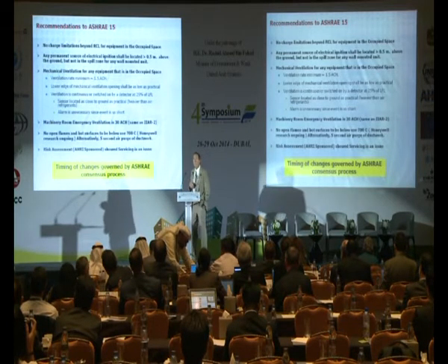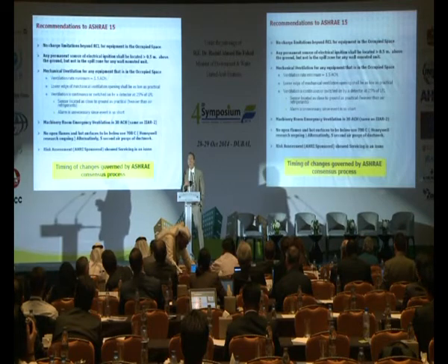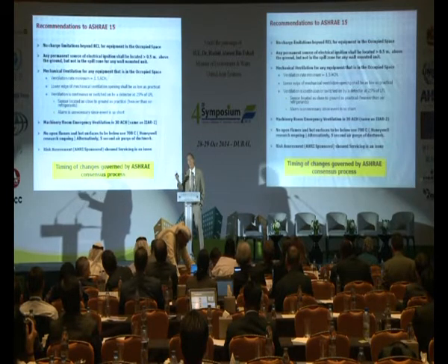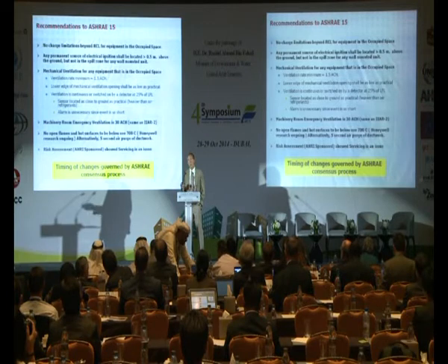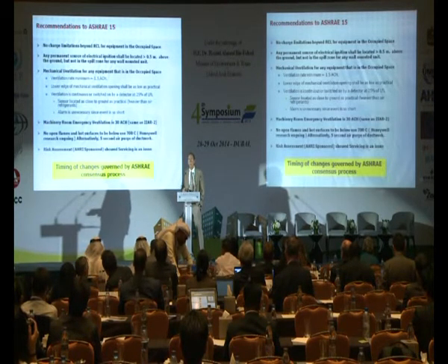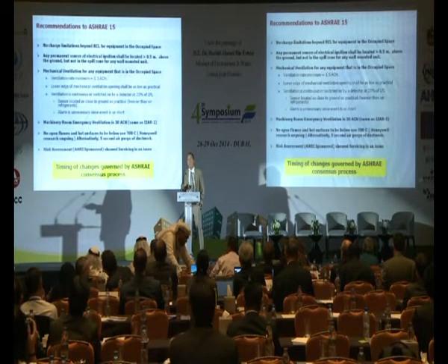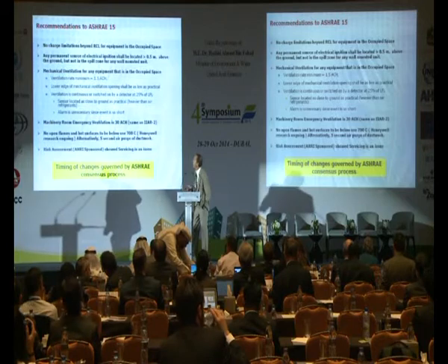For ASHRAE 15, we won't have any charge limitations beyond the RCL calculation. That's quite a bit different than you heard in 5149. Very simple to administer. The RCL calculation is woven into the United States design fabric, and so people are comfortable in doing that. We didn't see any need to limit the charge beyond that.